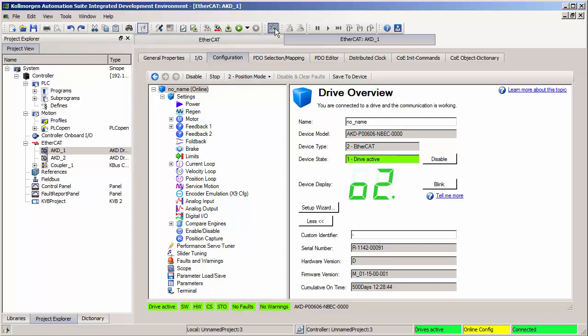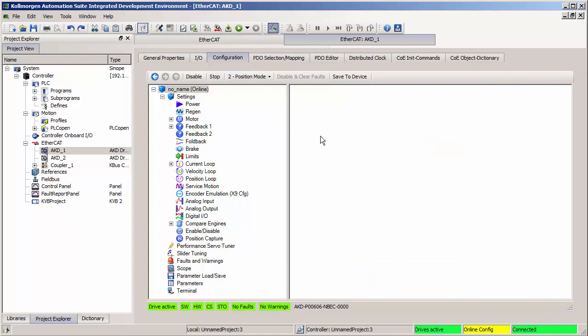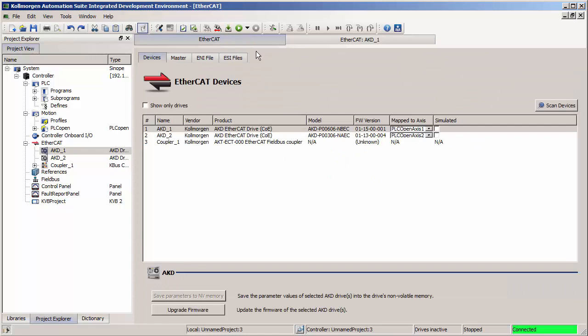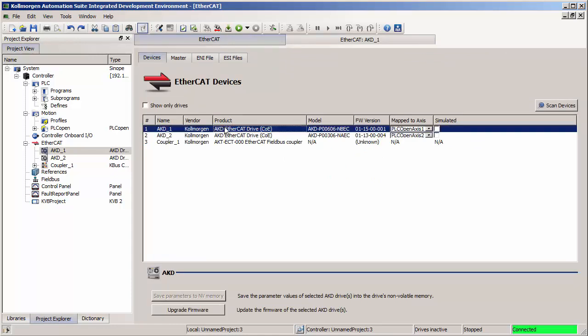If I turn off online configuration mode, the configuration screen shows disconnected. But now I can go back to the main EtherCAT tab, and after I've done a scan for devices and all my AKDs in the system are found, I can highlight one or multiple, and then this Upgrade Firmware button becomes active. If I press it, there will be a pop-up and it will let me choose a firmware version. You can download up to eight AKD drives at once, all through the Ethernet cables going from the PDMM controller to the AKD drives.